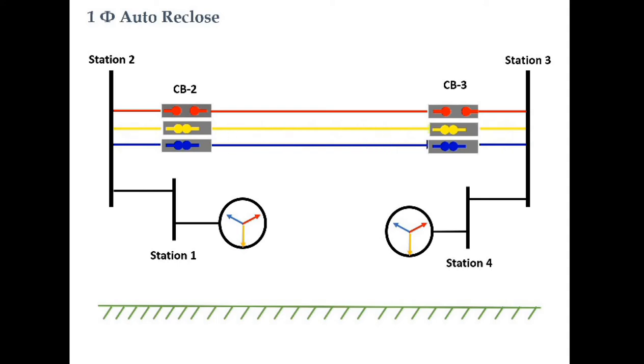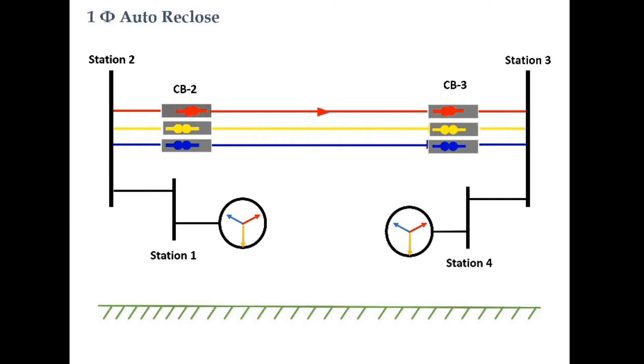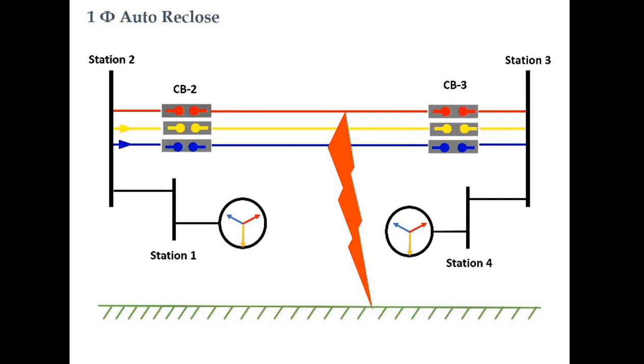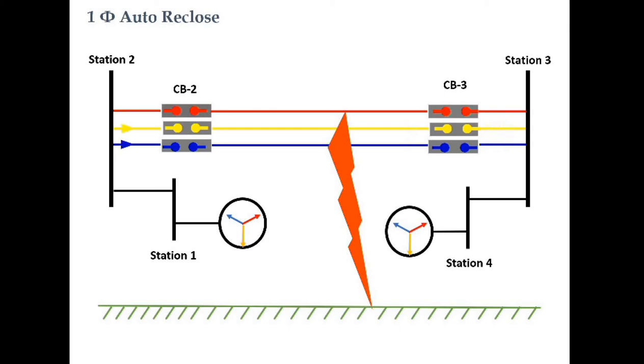In case of a transient fault, the fault will be removed within one second, so on reclosure of the circuit breakers after one second, the line will withstand and work normally as before. But if there is a permanent fault not cleared within one second, after reclosing, the relay will sense the fault once again and give a trip command to the circuit breaker. Tripping of the line after auto reclosure is called unsuccessful auto reclosure. In India, a single attempt of auto reclosure is followed, but in the relay we can select the number of auto reclosure attempts.